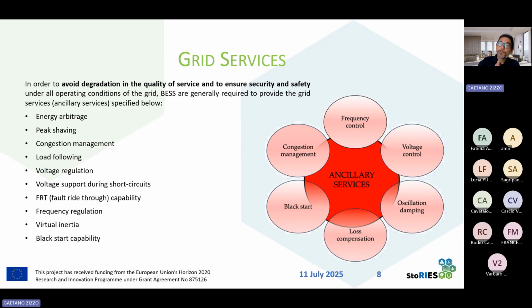The services normally are related to the control or to the regulation of frequency and voltage. But they are also related to the capacity to maintain the battery storage system in service also during a fault, or to use the same battery for creating a new grid after a blackout.